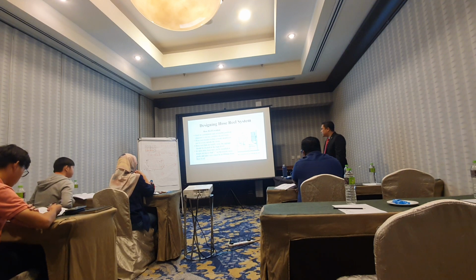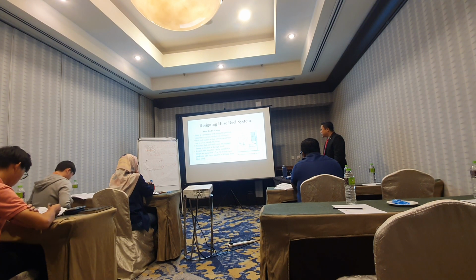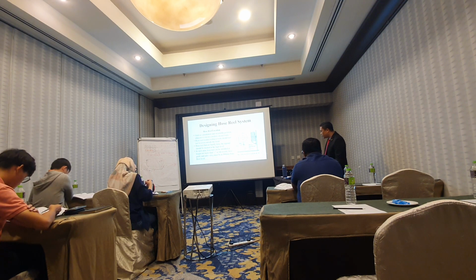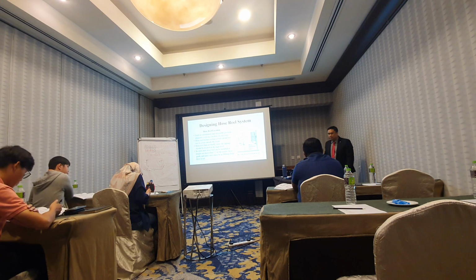In the open area, hose reel can be installed at a height not more than 1.7 to the nozzle, but the inlet valve must be at 900 from floor level. So, ni kan yang tuan tanya semalam.